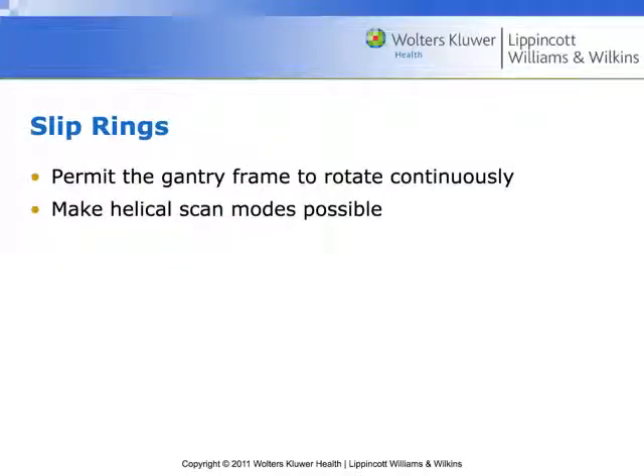The main purpose of slip ring technology is that it allows the gantry frame to rotate continuously, and this is what makes helical scanning modes possible.